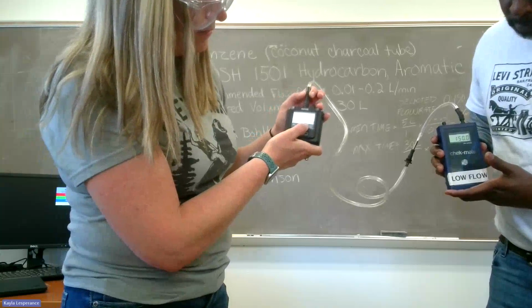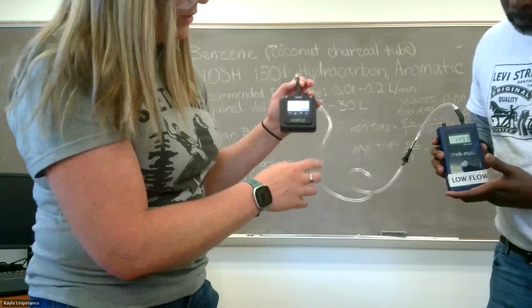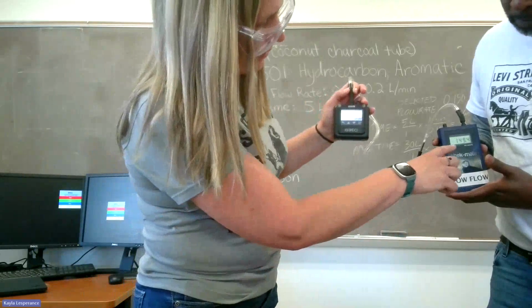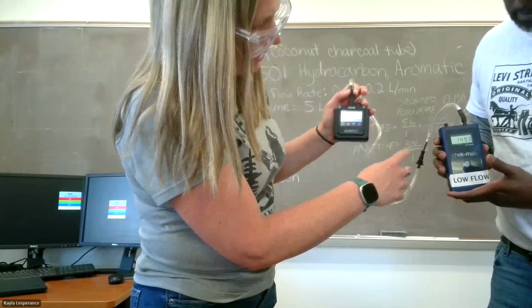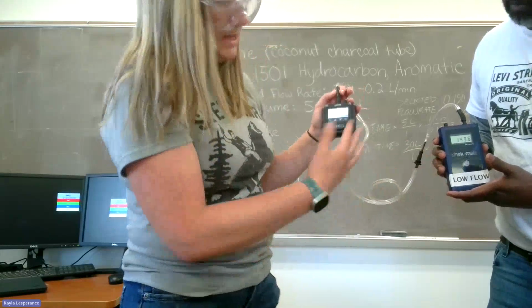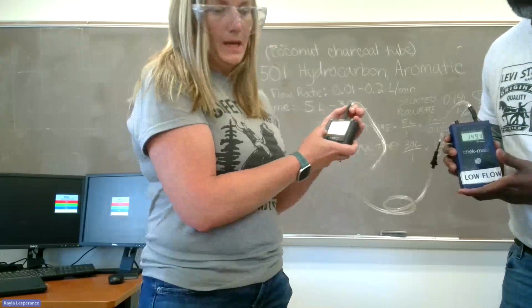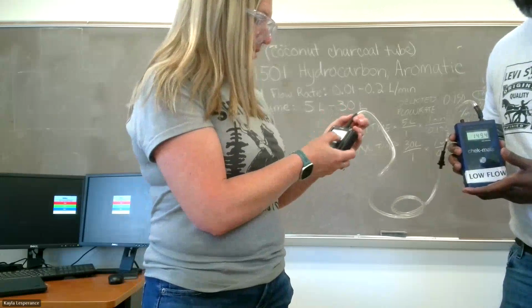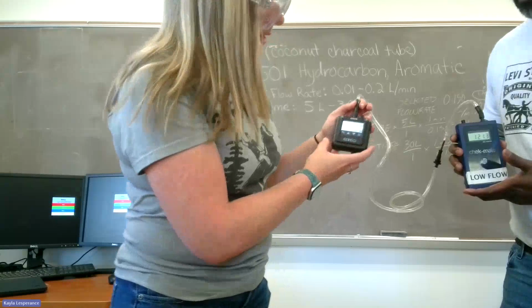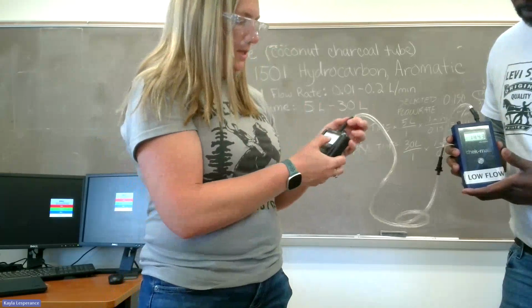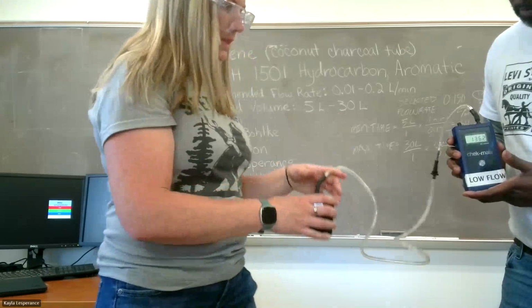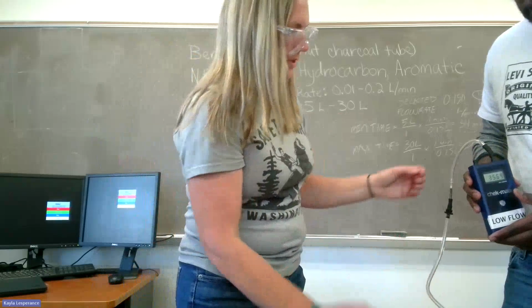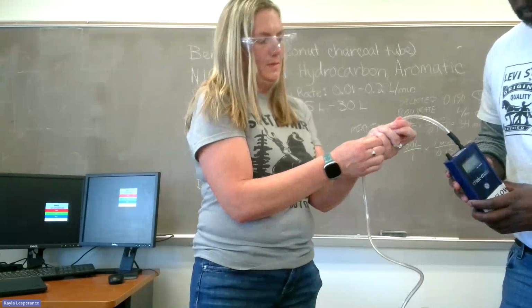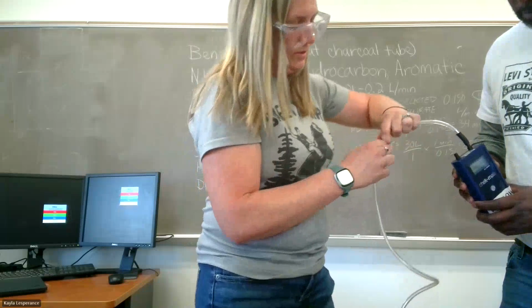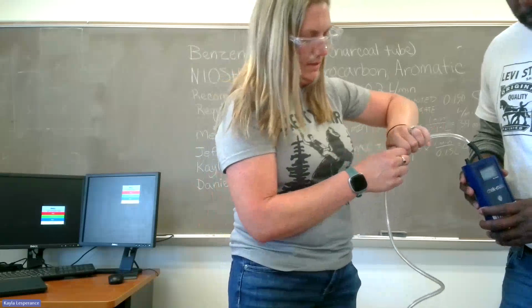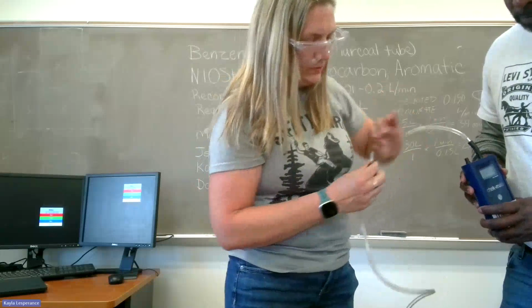So we want to take an average of at least 3 flow rates. So we record, we're at 149.4, and then 149.3, 149.5. So we would take all of those and average them and use that as our pre-flow rate. So we calibrated it. And we can start our sample time. So we're going to pause and have that ready to hang on our worker as soon as we disconnect the media. So this is our calibration media. That's going to get capped and preserved to do the post flow rate.